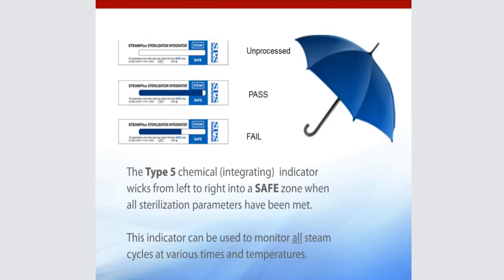If you've not seen a type 5 integrating indicator, it looks a little bit different from a regular chemical indicator because it has a chemical pellet usually that melts, and it's a moving technology across the front, almost like a thermometer, until it gets into the safe zone. And the reason these are used is with biological indicators, or you use them in between when you're doing your BIs. If you do a BI on Monday and you're not going to do another BI till the following Monday, using a type 5 integrator once a day in your sterilizer gives you that umbrella policy, that peace of mind that the sterilizer is functioning appropriately, because this is the closest thing you have to a biological indicator. It doesn't replace it because there are no viable organisms on there, but it reacts over the time of the cycle, not just at one specific point in time.